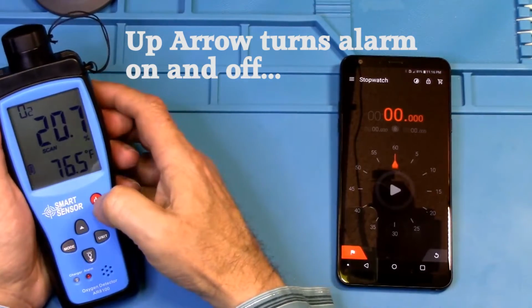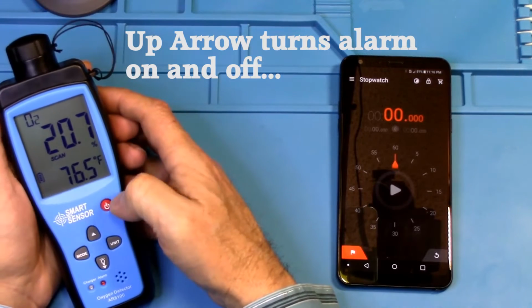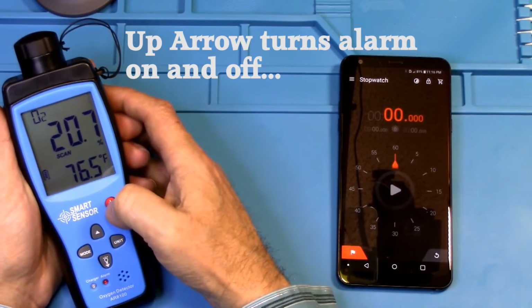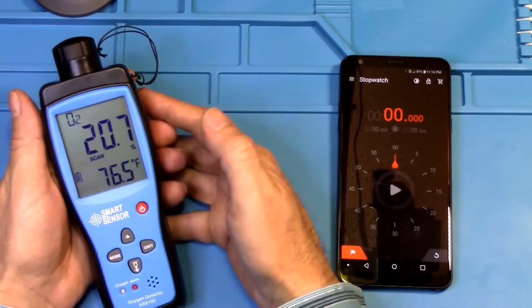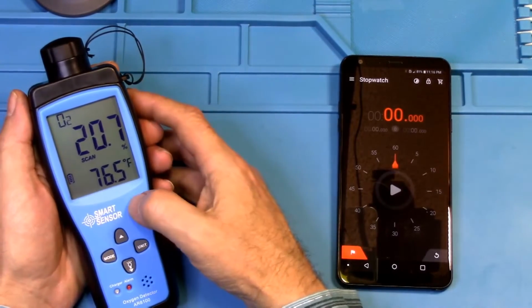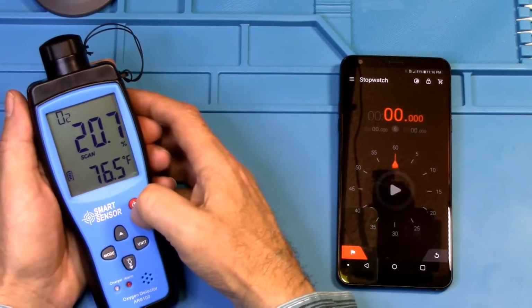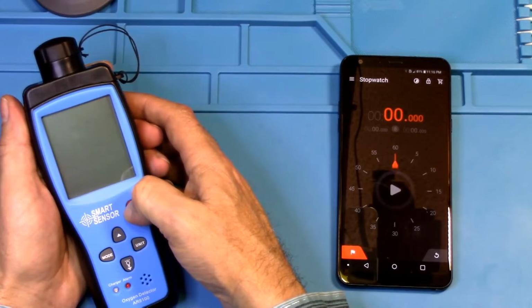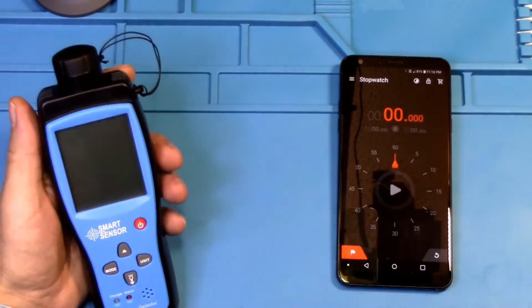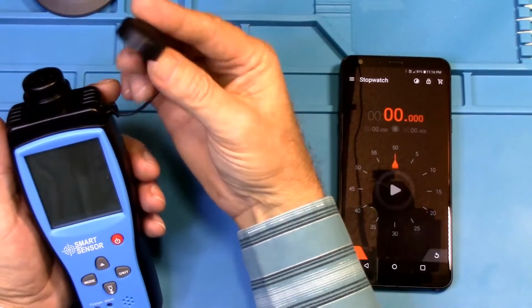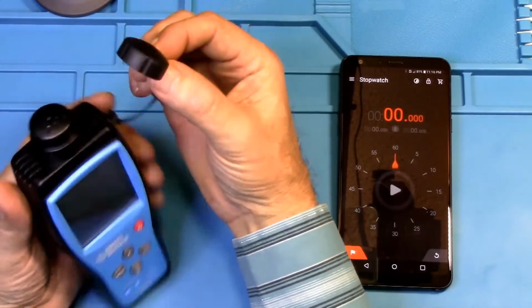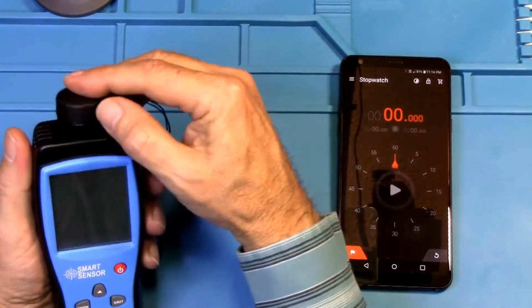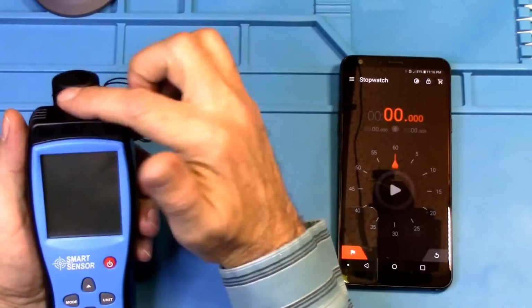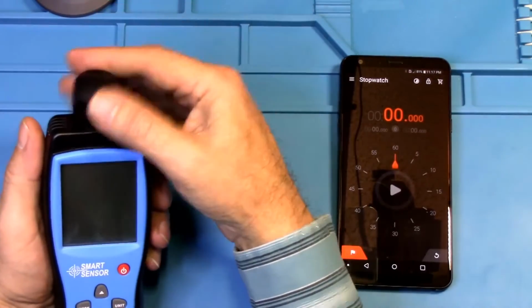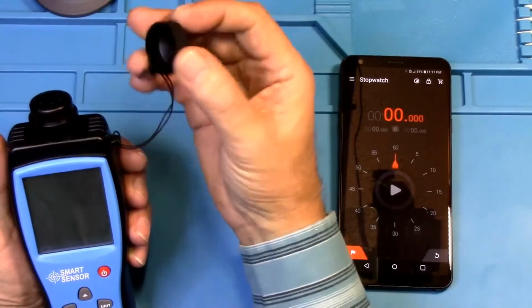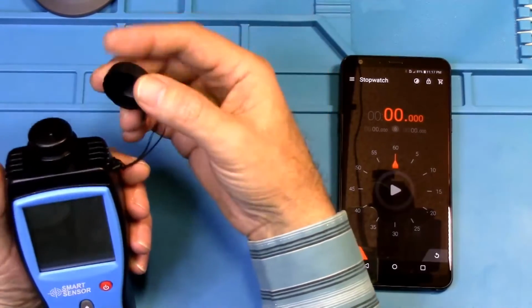Now I'm going to show you how to zero calibrate this device. Okay, if your device is on right now, turn it off. So turn the power off, hold the power button down, turn it off. Don't get rid of your cap. I see some people getting rid of the cap. Don't do that. The reason for that is this cap protects the sensor from dust, and moisture. So yeah, don't take this cap off and throw it away.